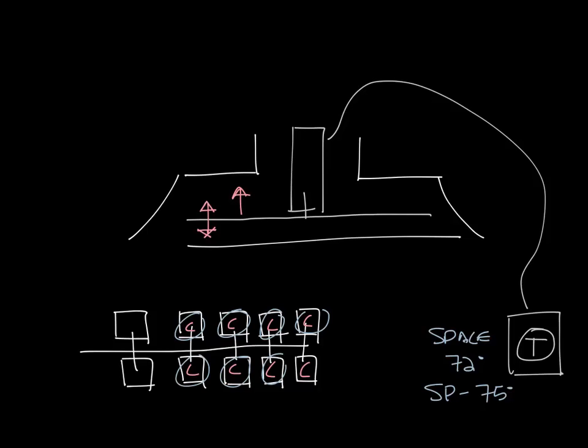You can do that by putting in pressure control with a bypass box or a pressure relief damper. I mentioned these in my original VAV diffuser podcast. But another easy way to provide pressure relief is to put in a relief ring on the diffuser. So a relief ring looks something like this. It'll mount to the neck of the diffuser, and it is oversized by 2 inches.